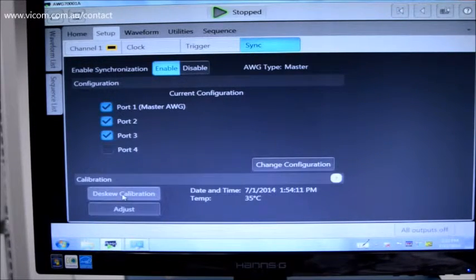So basically that's the whole process. Once you've done this calibration, then you can change sample rate, you can power down the units and then power them back up again, and they will continually be synchronized. If you're using a trigger, basically the master controls the trigger selections.